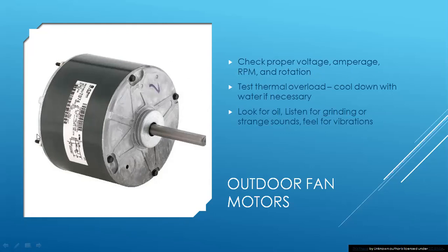So if you're replacing a fan motor, it's important to, number one, know your rotation. Some of them you can change. Some of them are fixed. Also make sure your RPMs are correct. If you've got a low RPM and you put a 1050 in there, chances are you're going to overheat the unit.